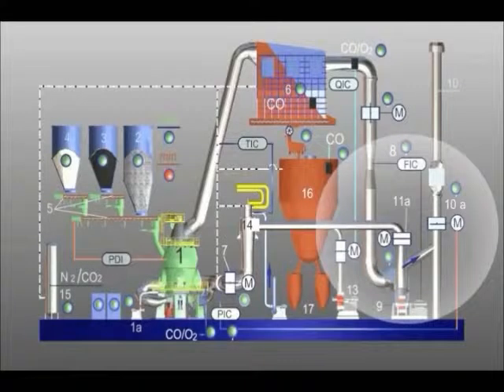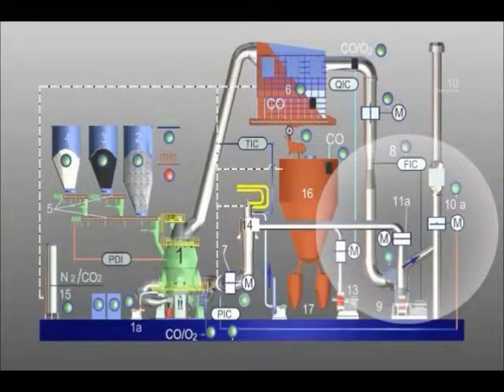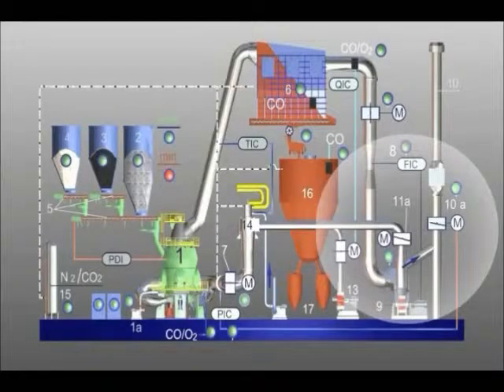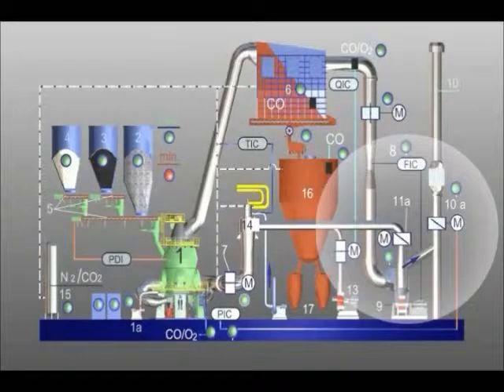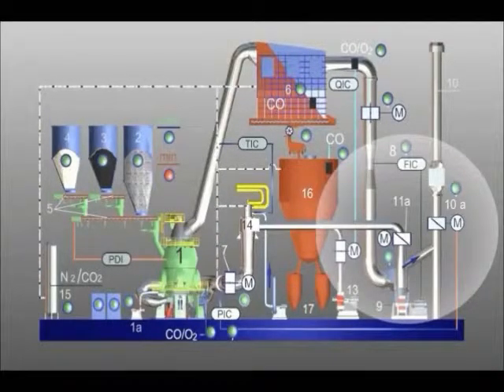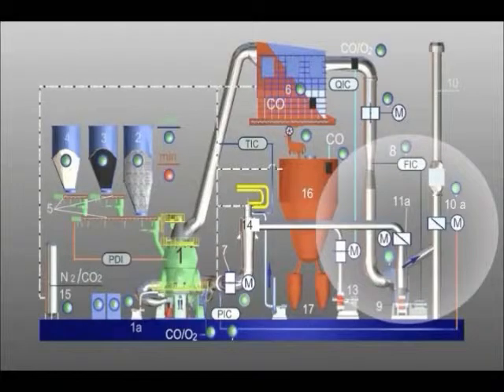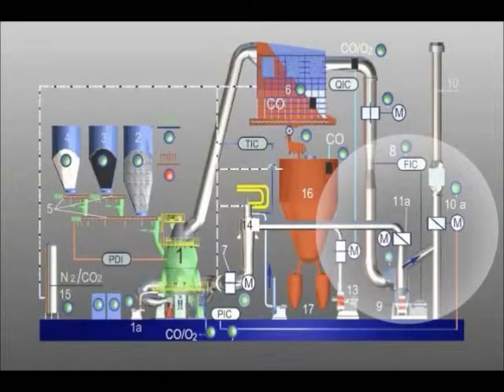The flap in the return gas duct at position 11a and the stack flap at position 10a for controlling the volume flow of exhaust gas are moved to their start position. The volume flow of process gas is measured via a venturi tube at position eight. This volume flow is regulated by means of the vane control at position nine.